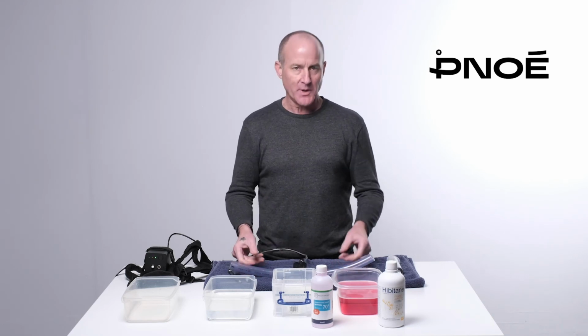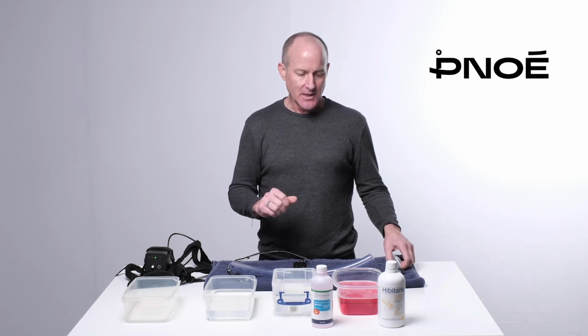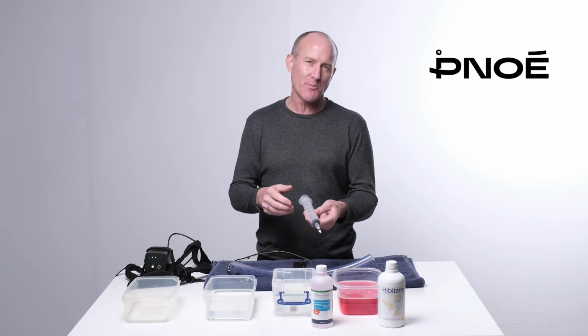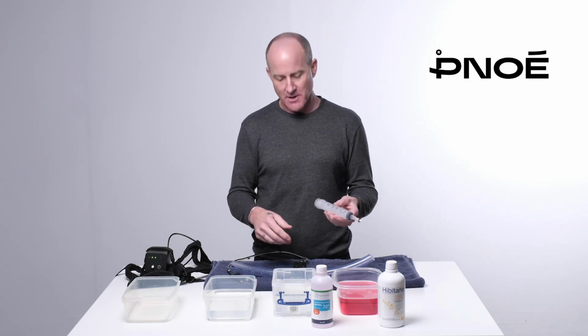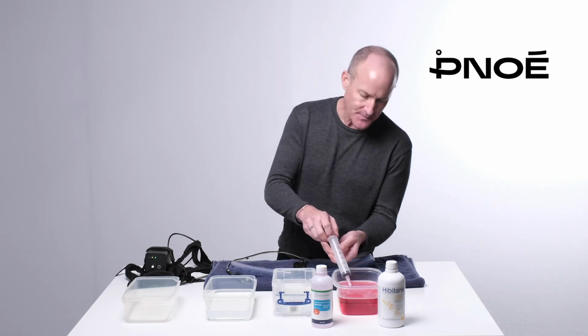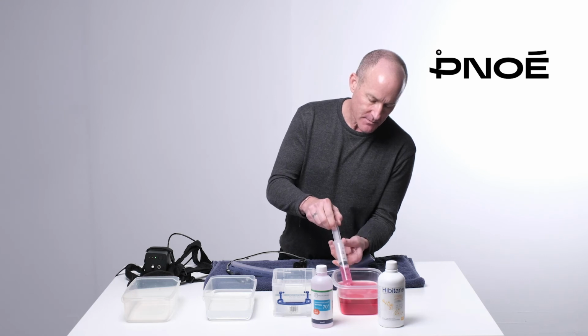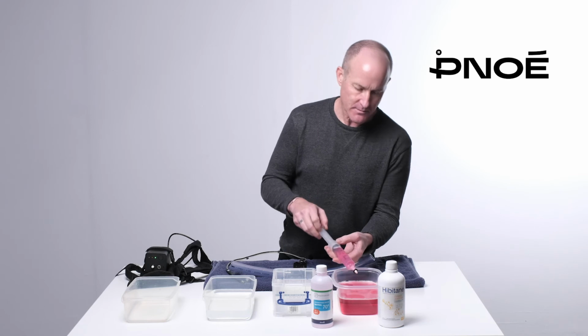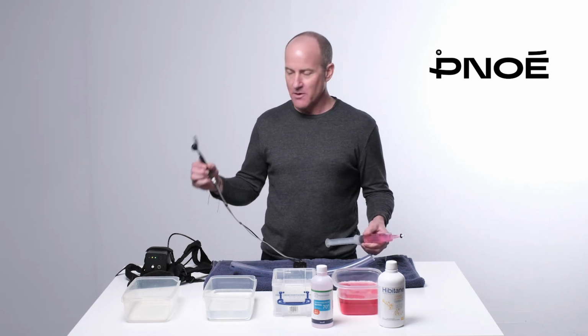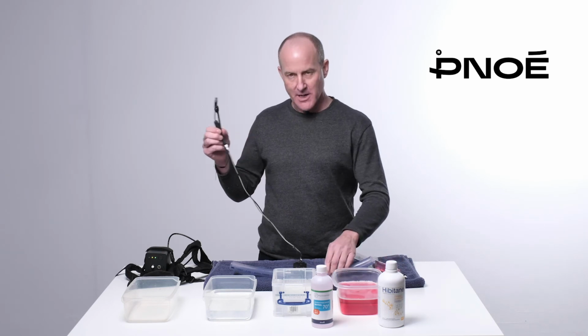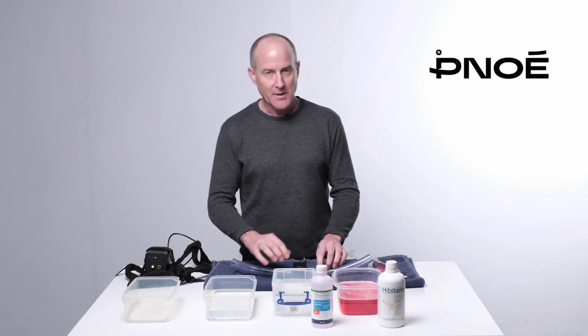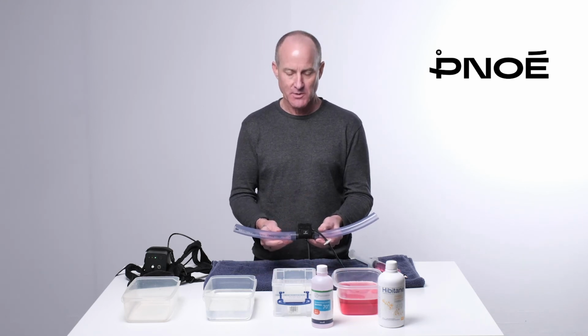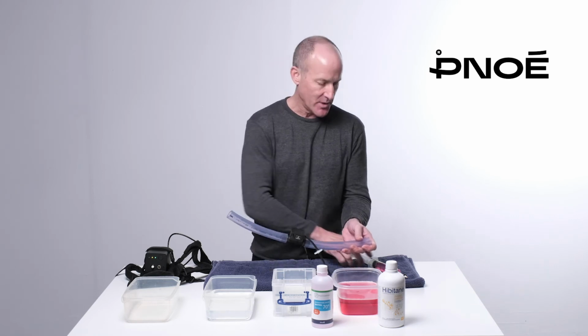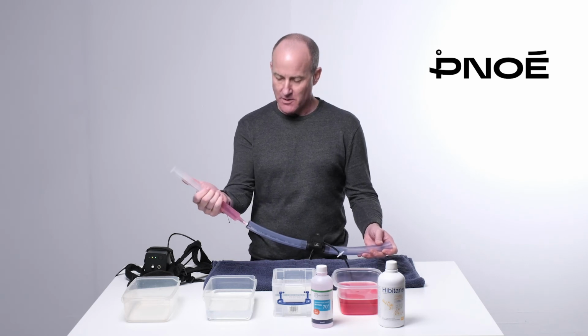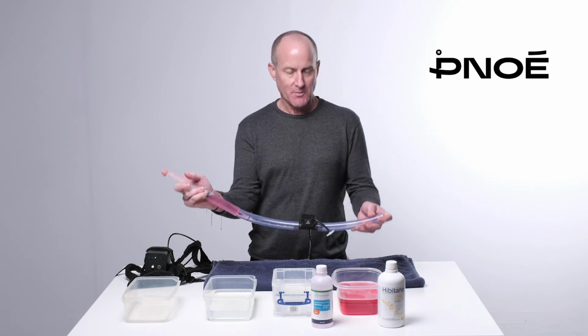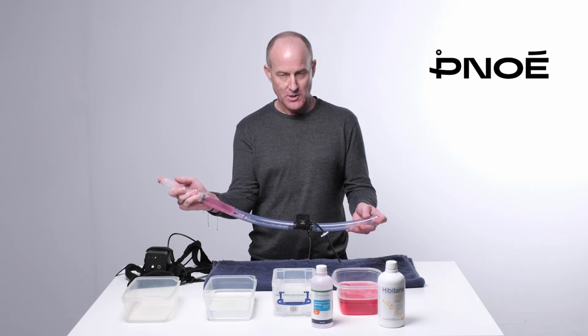So the first solution will be the diluted Hibiclens or HibiTane. We use a syringe to make things easier, and you require approximately 60 mils to have enough liquid in there to fully cover all the parts within the flow sensor. Again, make sure that your flow sensor line and the power cable are completely away from any of the liquids. Make sure none of the liquid can touch any part of the flow sensor itself. So what you're going to do is slightly cant one side, and put the solution into the tube, making sure you keep an even balance so that the solution doesn't fall out the other side.